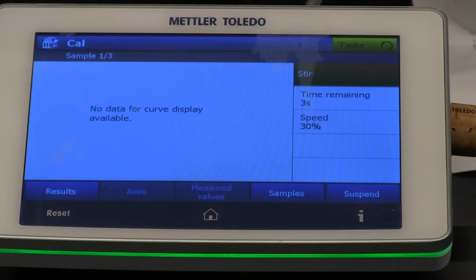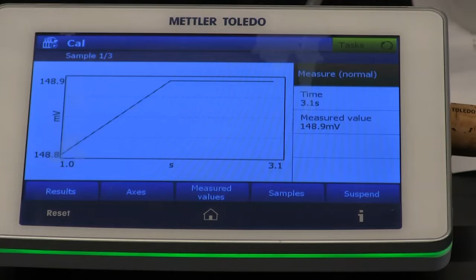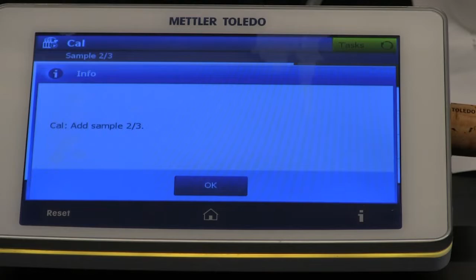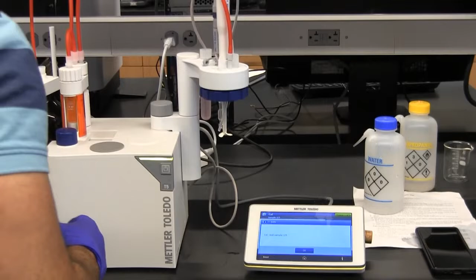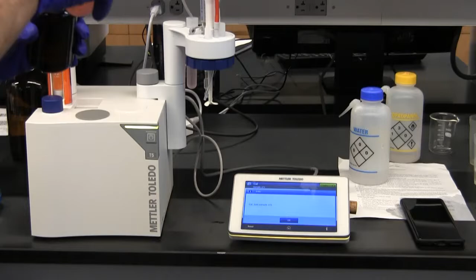Also make sure nothing in the cup is touching each other, so the line is not touching the fan, and is not touching the pH sensor. It gives you a quick curve like this. You don't click OK until you remove your sample, clean everything and put your new sample. In order to preserve this pH, you just put it back in its bottle and put it in the fridge. Now we have our pH of 7.